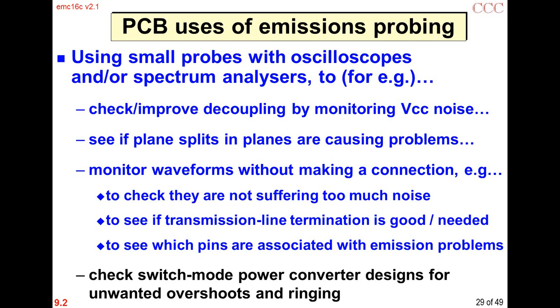Anyway, don't do it. Don't float your scopes, that's very bad. Never take the ground lead off. If you don't have a differential amplifier with high voltage withstand capability, use a close field probe with suitable insulation instead, one that will withstand a kilovolt or two, not just something rated for 60 volts.